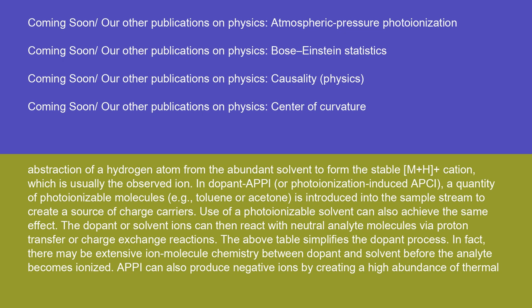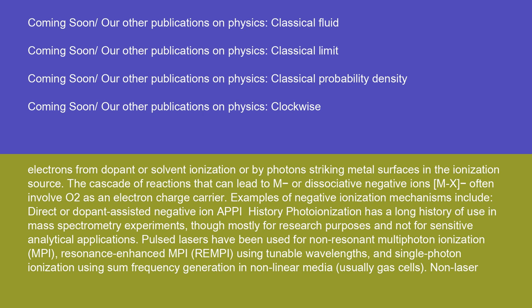In dopant-assisted APPI, a quantity of photoionizable molecules, e.g., toluene or acetone, is introduced into the sample stream to create a source of charge carriers. Use of a photoionizable solvent can also achieve the same effect. The dopant or solvent ions then react with neutral analyte molecules via proton transfer or charge exchange reactions. In fact, there may be extensive ion-molecule chemistry between dopant and solvent before the analyte becomes ionized. APPI can also produce negative ions by creating a high abundance of thermal electrons from dopant or solvent ionization, or by photons striking metal surfaces in the ionization source. The cascade of reactions leading to M−• or dissociative negative ions [M-X]− often involve O2 as an electron charge carrier.